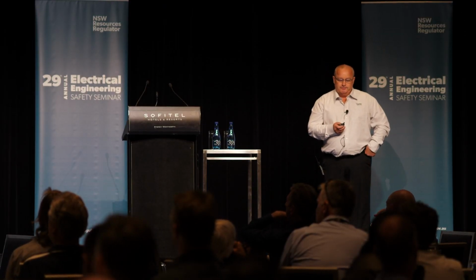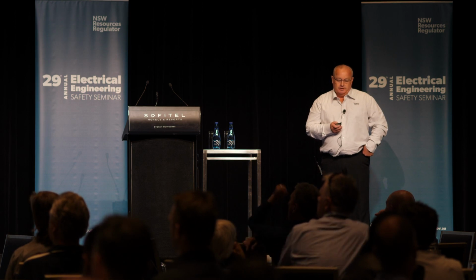Next was the reduced voltage on the fault conductor in relation to the station earth. So we measured at the corresponding substation for low impedance: 1900 volts in 85 milliseconds, 750 volts in 500 milliseconds, and 250 volts in 2 seconds. So now they've gone from a high impedance system to a low impedance system, where the currents are a lot higher. During the diagnostic tests, they found that the fault current needed to be limited to around 0.5 of an amp or less. And one of the key issues is the thermal energy, which actually creates the spark and the fire, limited to 0.1 of an amp squared second. So that's the current distribution in the ground on the faults.